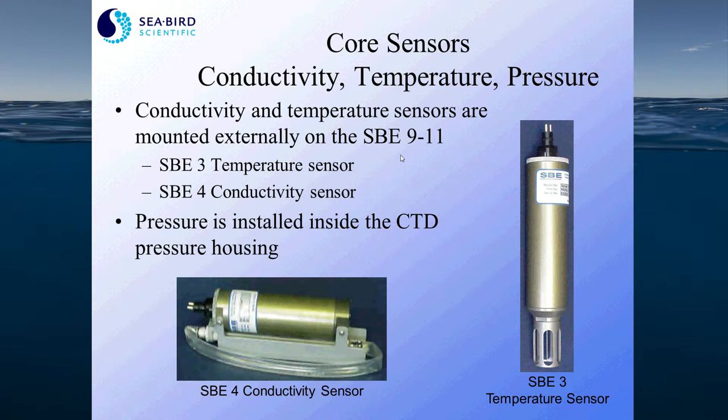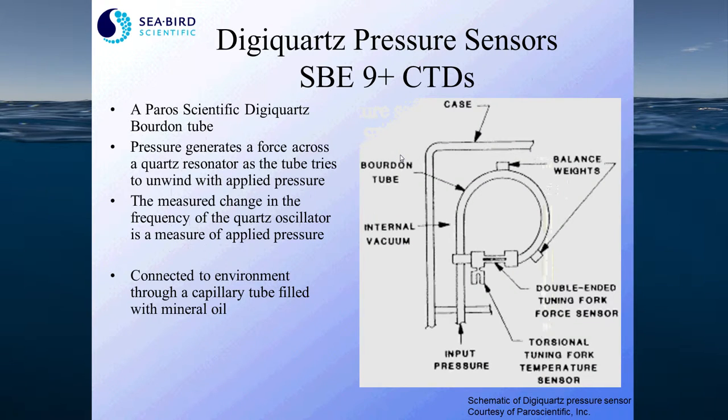The pressure sensor is typically housed internally to protect it from shock and rapid temperature changes. We measure the temperature at the pressure sensor itself and mathematically compensate for any temperature effect on the output. All 9 Plus CTDs use a Paros Scientific Digi-Quartz Bourdon tube sensors, shown here on the right. Pressure generates a force across a quartz resonator as the tube tries to unwind when pressure is applied, and the measured change in frequency of the quartz oscillator is what we measure to output applied pressure.